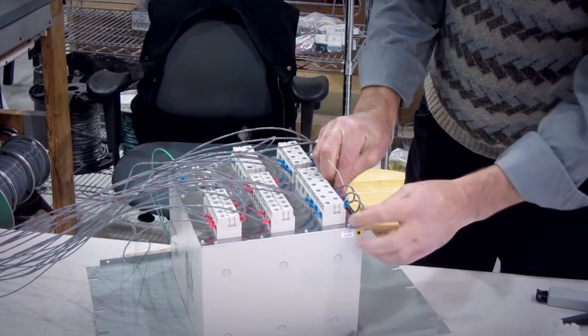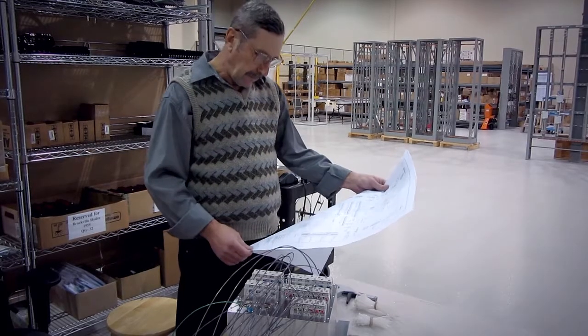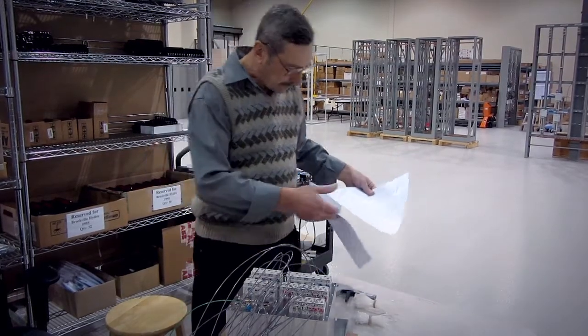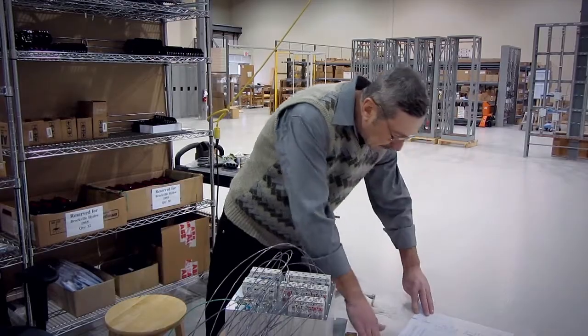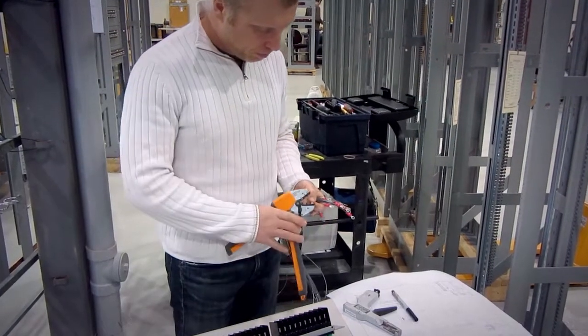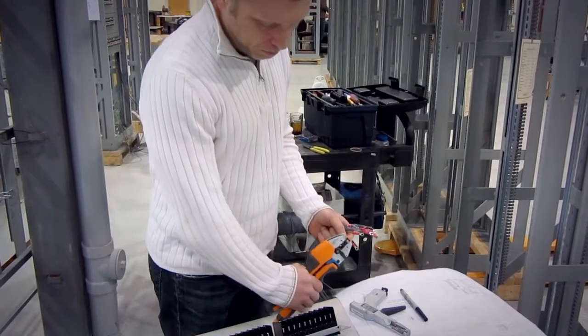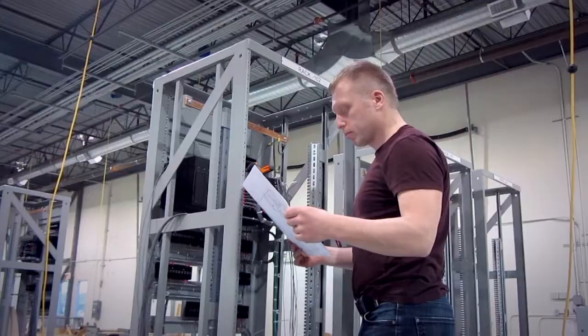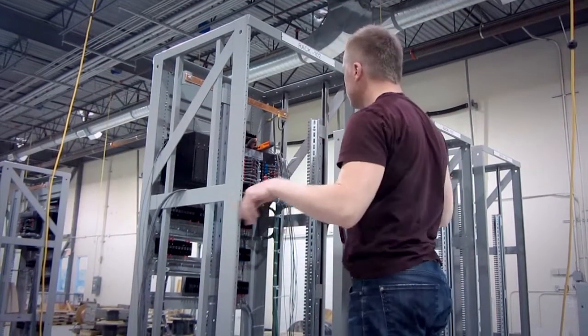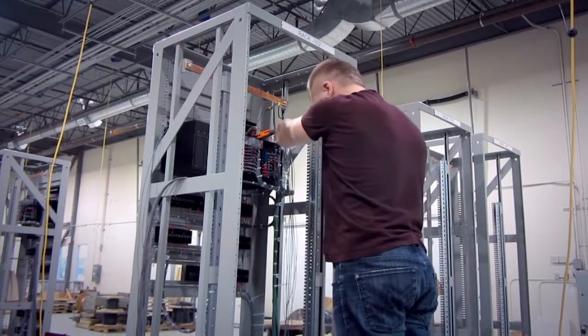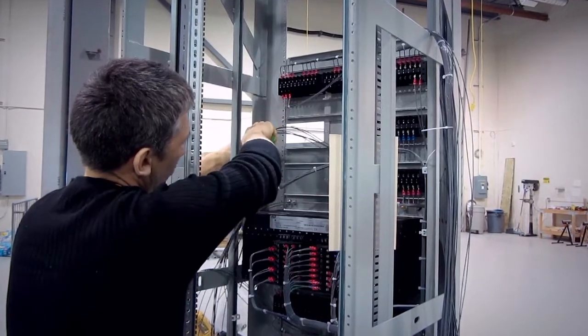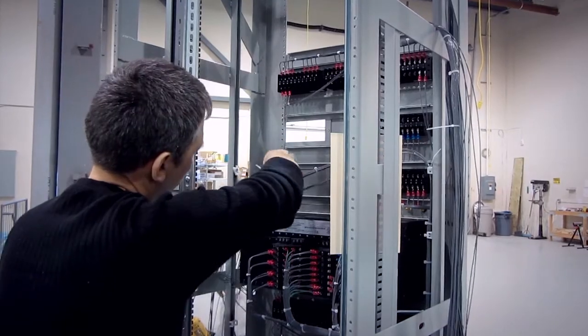Electricians receive the Issued for Construction Wiring Diagrams, or CWDs, as they're commonly referred to in the industry. These drawings detail the wire types to be used and the connections to be made. Alternatively, complete in-panel direct wiring from top to bottom is also undertaken. Once again, the panel gets the usual Virelec attention to detail in terms of careful arranging of wires and looms.